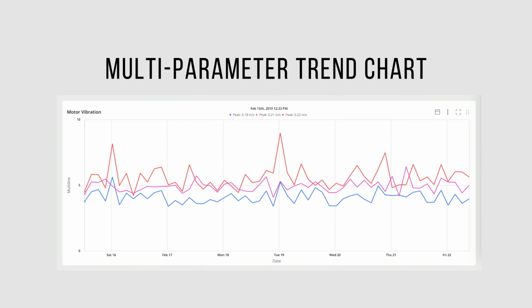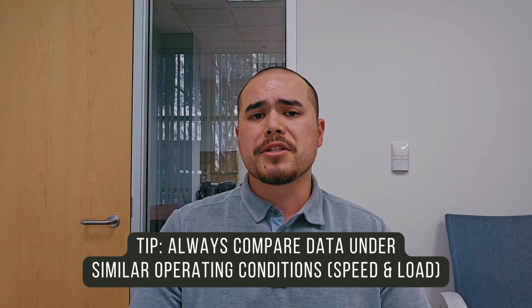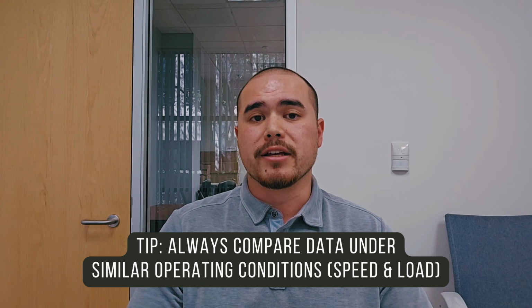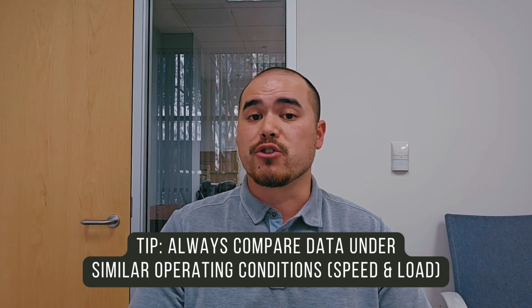You can also trend non-vibration data like speed, temperature, or process variables to add more context. Some platforms, like Petasense Aero, let you overlay multiple parameters on the same chart, making it easier to spot patterns, like how vibration changes with temperature or running speed. One tip when using trend charts is to always compare data under similar operating conditions, especially speed and load. Otherwise, you might confuse normal operating changes with potential faults.